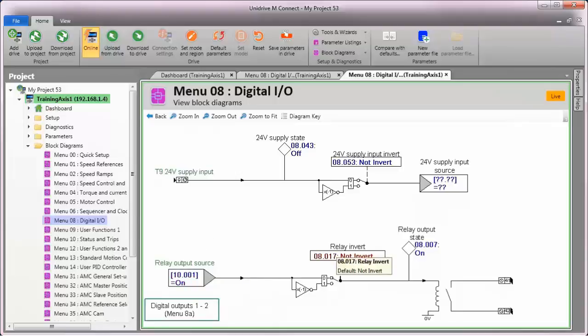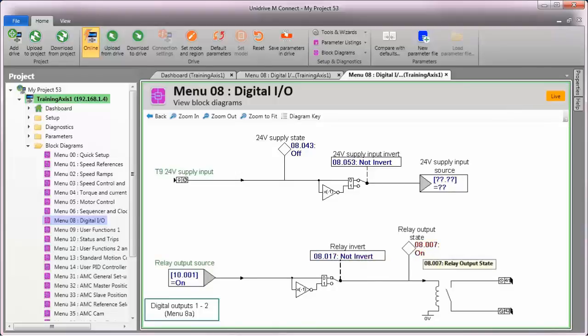Menu 8, parameter 17, which has the effect of making the relay contact either normally open, which is the default function, or normally closed if I activate it.